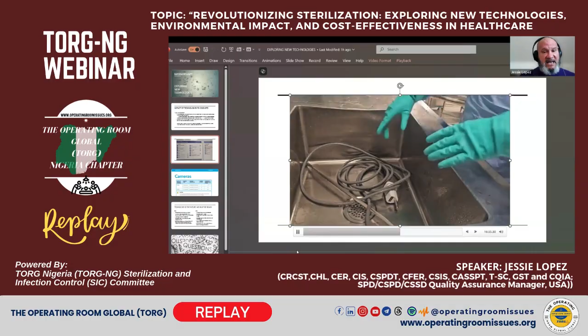Now this device is ready for the next step in the IFU, which is ultrasonic cleaning. Now, I have to put a word on ultrasonic cleaning because there are different types of ultrasonics. There's actually 6 different types of ultrasonics. The one that you see pictured here is actually an ultrasonic irrigator cleaner disinfector. Okay, so it's going to give you ultrasonic capability. It's going to clean your device.